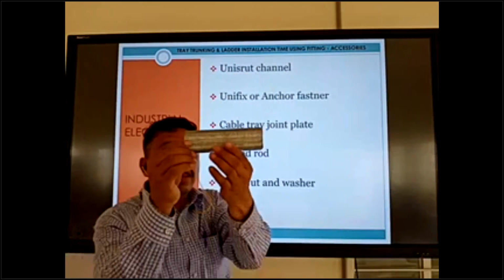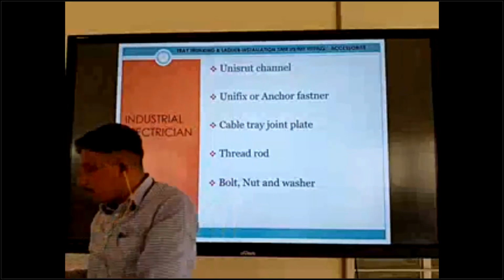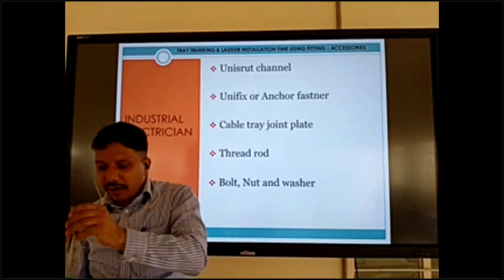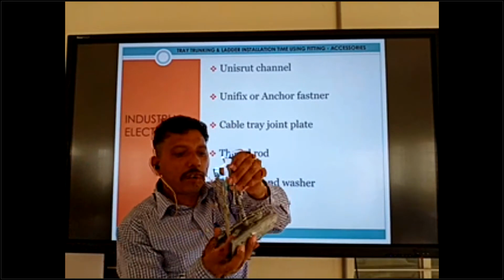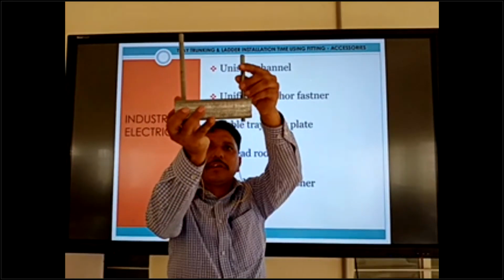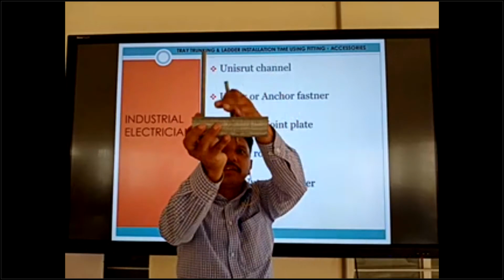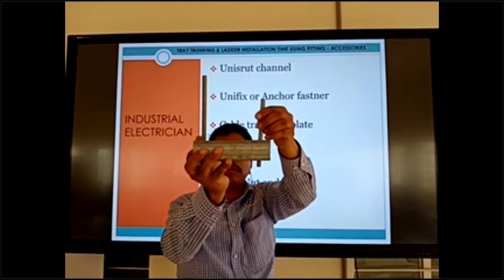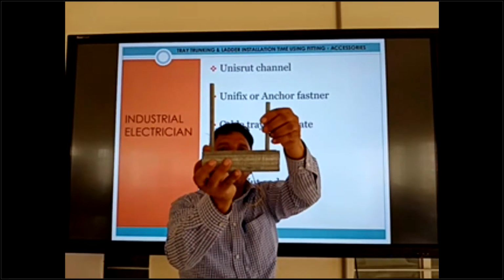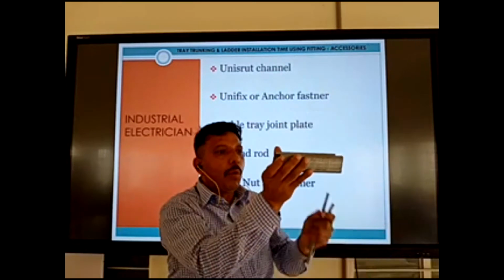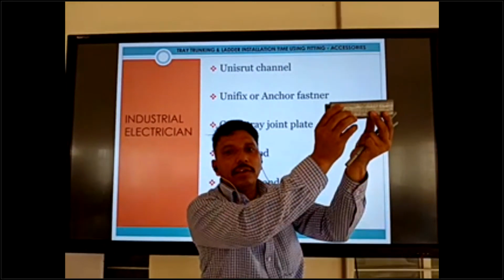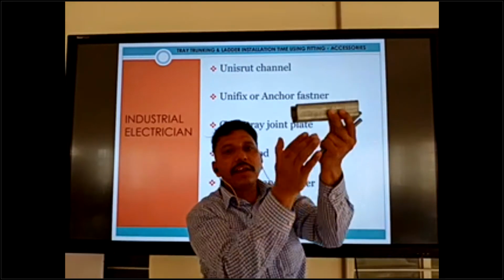We can put it like that and put the two rods there. In the hanging system, we use this hole and put the two rods like that, hanging, and inside this cable tray is running. Very easy, you can see. In slab, if you install in slab, or if you install in wall, we use the channel directly on the wall - this channel, we make the A type channel and install the channel only.